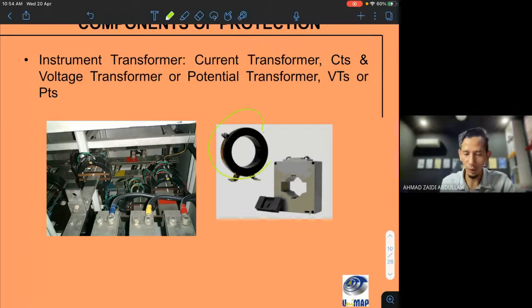Okay, next, this is the current transformer I just talked about. This is a sample of a current transformer, bulat saja. So how to install the current transformer, you can see here. And this is the bus bar. For those yang tak pernah kenal bus bar, this is the bus bar. This bus bar is R Y B, and this one is neutral. So we need to put the current transformer through and through, so the bus bar must lalu ikut sini.